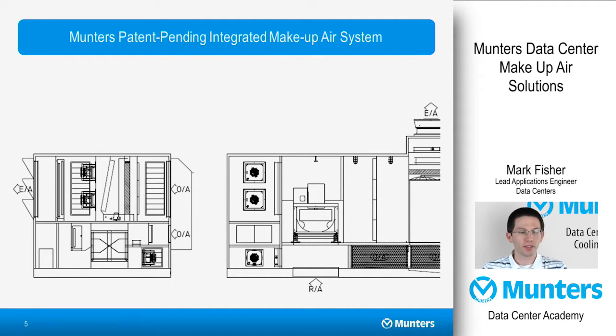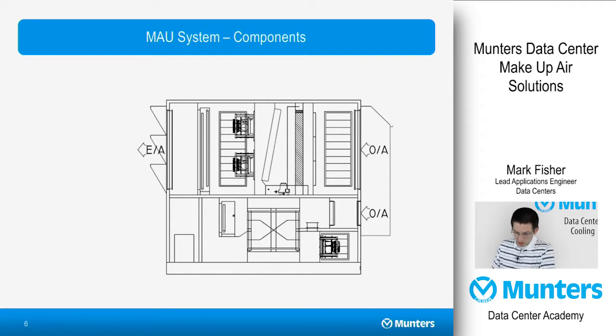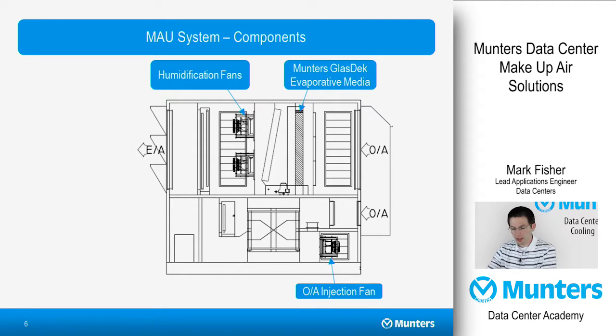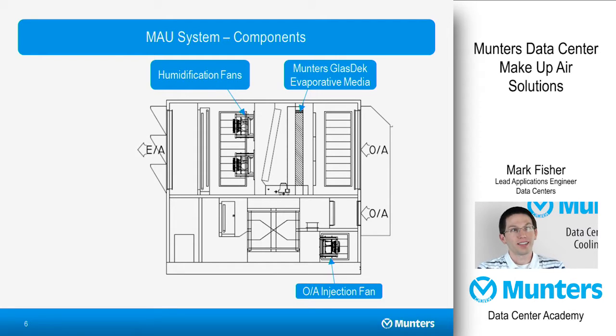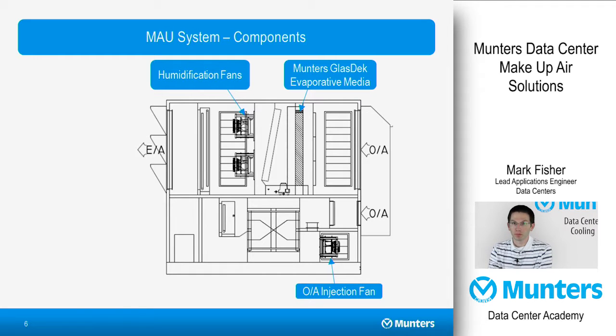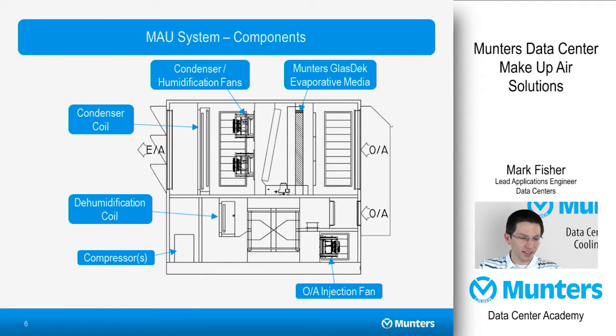This slide shows Munters' patent-pending integrated makeup air module system and its attachment onto a typical rooftop recirculating air handler. The basic makeup air system consists of the following components: an outdoor air injection fan to push the outside air into the recirculating air handler, and a Munters GlasDek evaporative media section to provide humidification in an energy-efficient way. We do this by taking return air from the air handler that's already heated from the data center and cooling it evaporatively, adding humidity without requiring any extra energy to heat up the air or water beforehand. The humidification fans then insert the air back into the recirculating air handler. In climates where outside air requires dehumidification, we can add a dehumidification coil, condenser coil, and compressors.